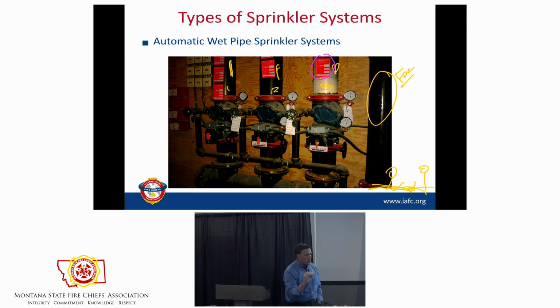So if we want to limit, we always want to turn off, after a fire event, the smallest part. So in this case, when we look at this riser, these are the control valves for each riser assembly. So if you feel it, sometimes you can tell which one's flowing, sometimes you can't. Sometimes you can look at the gauges and see what's fluctuating. Sometimes you can't, sometimes you got to look. So how we control it is that valve, not this.